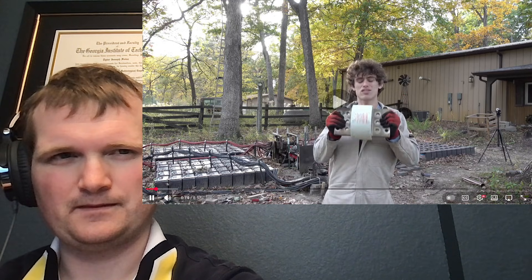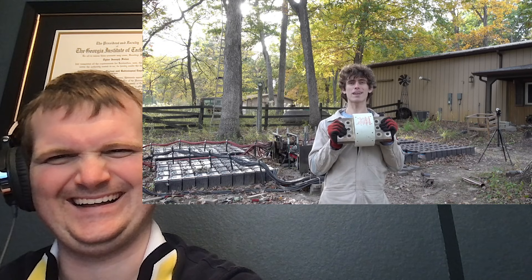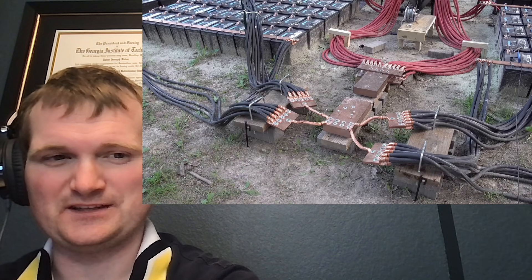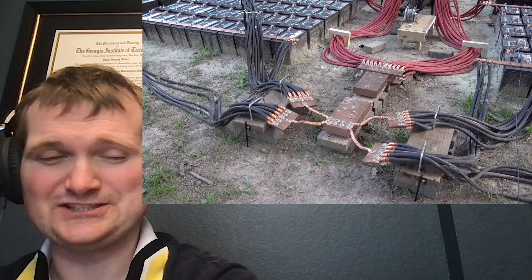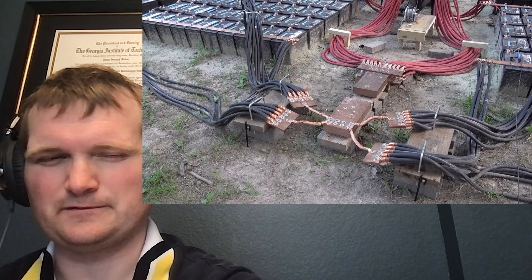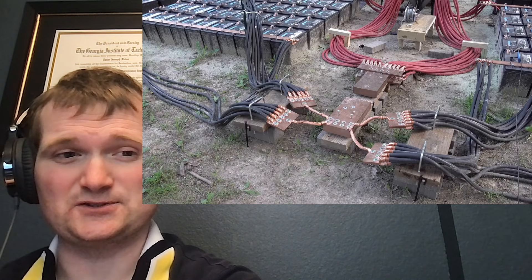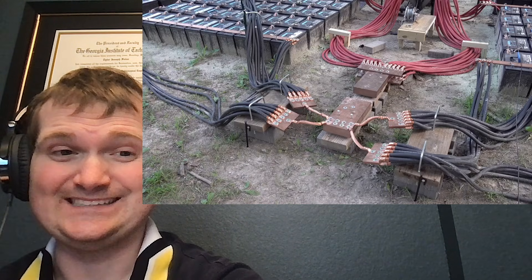Backup fuses can be in the range of 2,000 to 10,000 amps for large transformers. This monster weighs something like 45 pounds — it's the biggest fuse he could find online. It's not often that he can beat Photonic Induction at anything. You could also see a 6,000 amp fuse in the primary reactor coolant pump starters, and a reactor coolant pump is about the size of his house. In most industrial applications, 400–800 amps is still considered a big fuse.